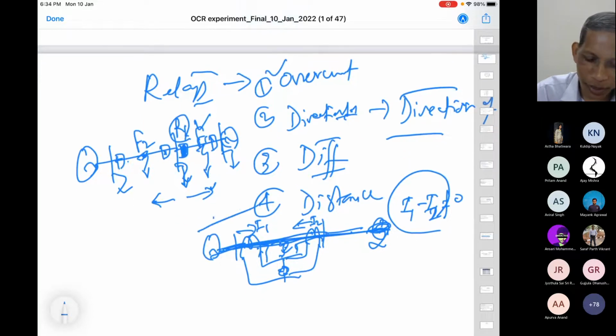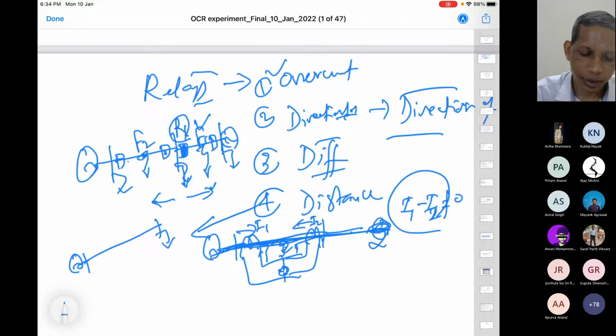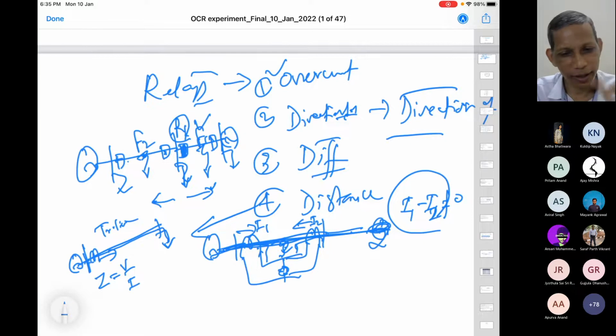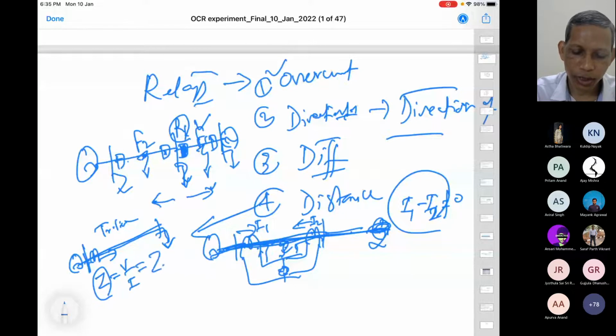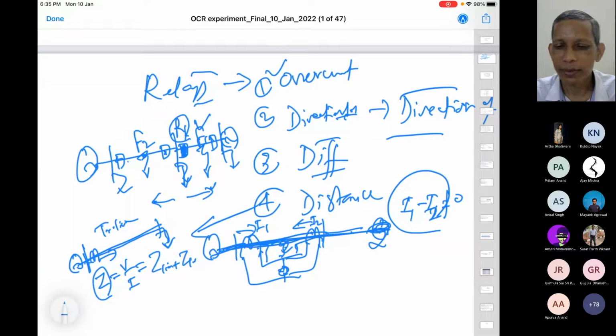And then, against a background of distance protection, we'll come to it later on also. Think about this: suppose this is a transmission system, a transmission line. Now think about the general idea that we would like to have the impedance. What is this impedance? Simple, at this moment V divided by I. Whatever voltage and current flows will depend upon this impedance plus the load impedance. Normally, if you have a voltage and current signal and can numerically calculate the impedance, it is nothing but the line impedance plus the Z load impedance. The impedance will normally be much higher.